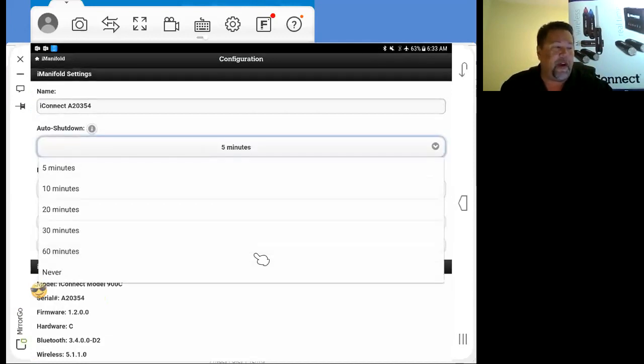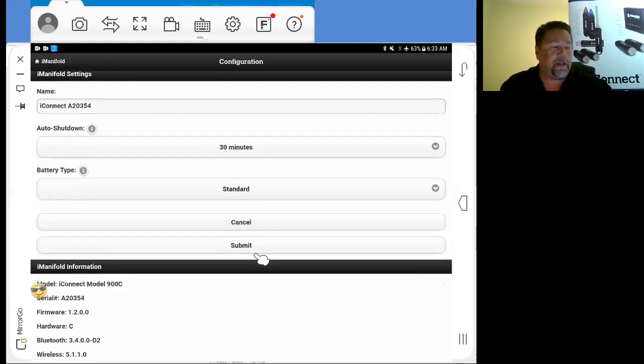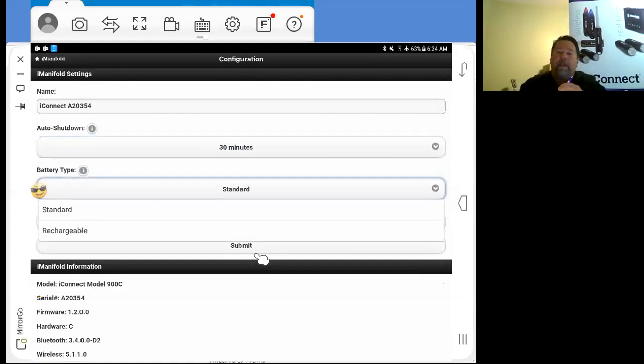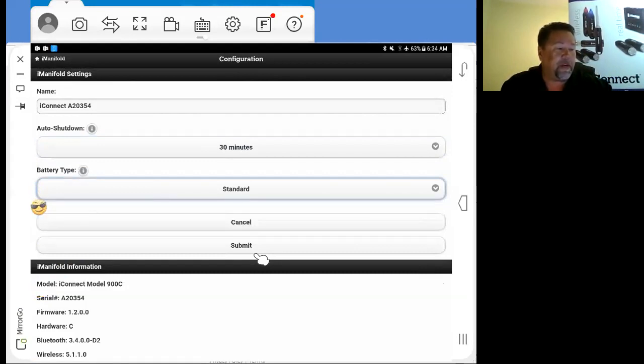Your shutdown time, simply tap the bubble, and you can go 5, 10, 20, 30, 60 minutes, or have it never shut down. Whatever you want, I'm selecting 30 minutes. And your battery type. Standard batteries would be for standard alkaline batteries and your lithiums. If you do use rechargeables, please select rechargeable. They discharge at a different rate than standard batteries, and it'll optimize the life of your rechargeables. So we're using standards. We'll keep the standards, and of course, we'll submit that.